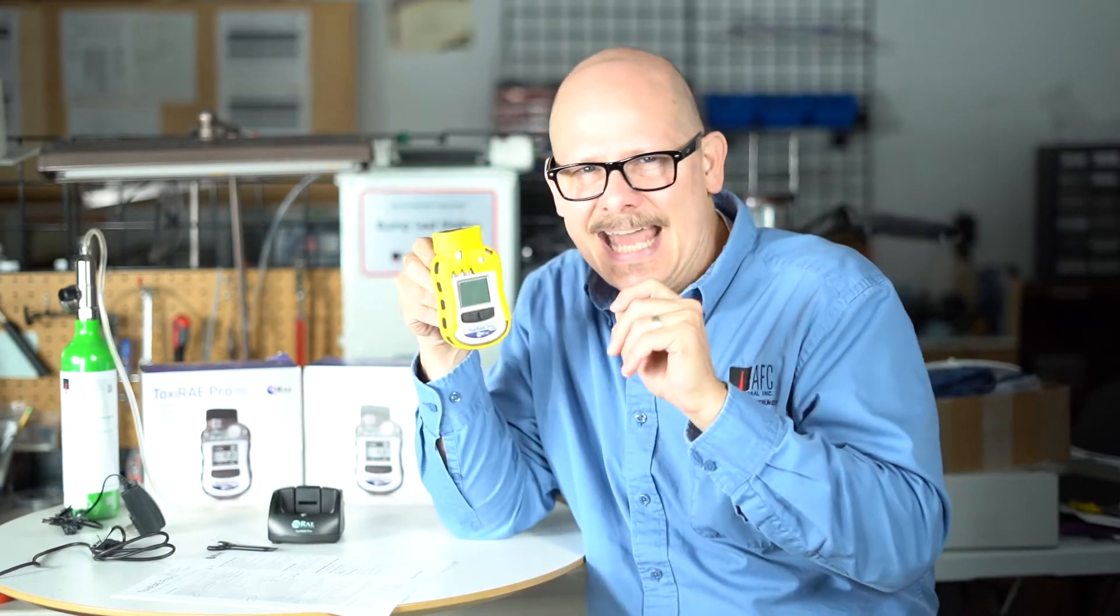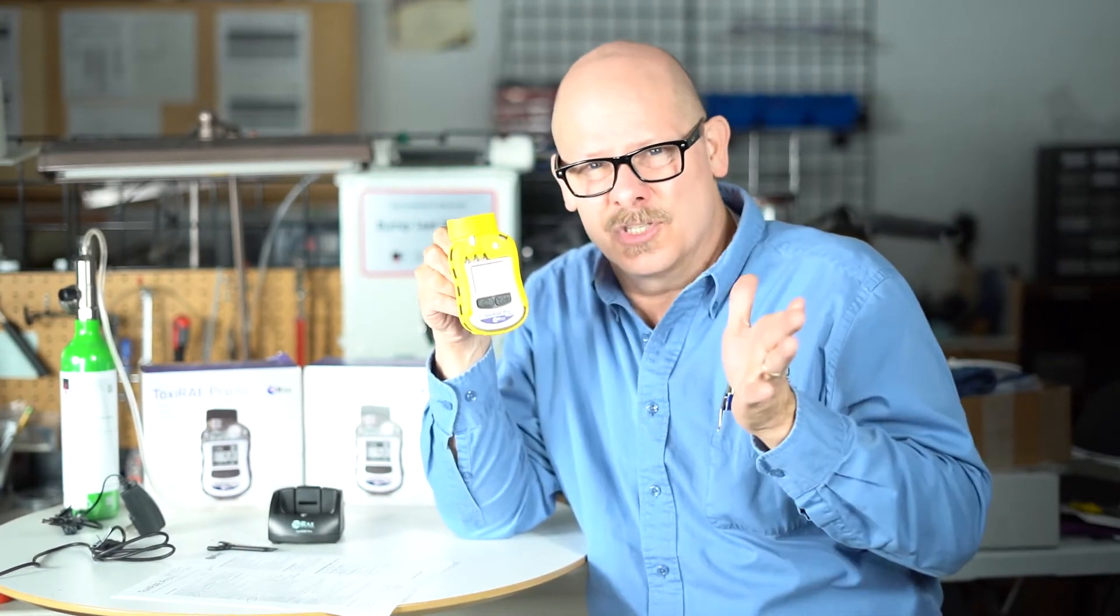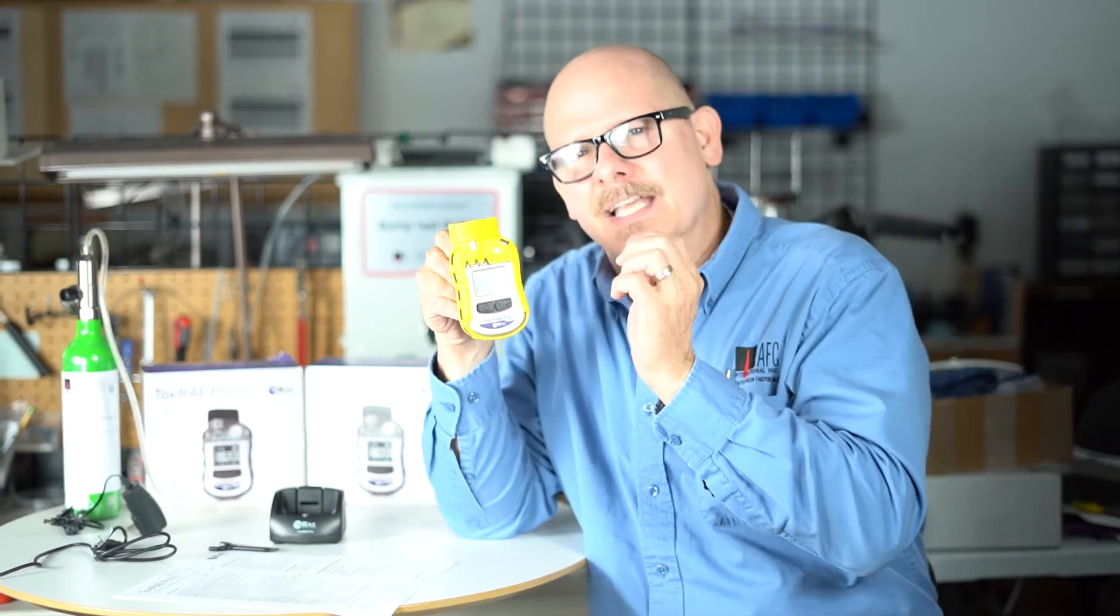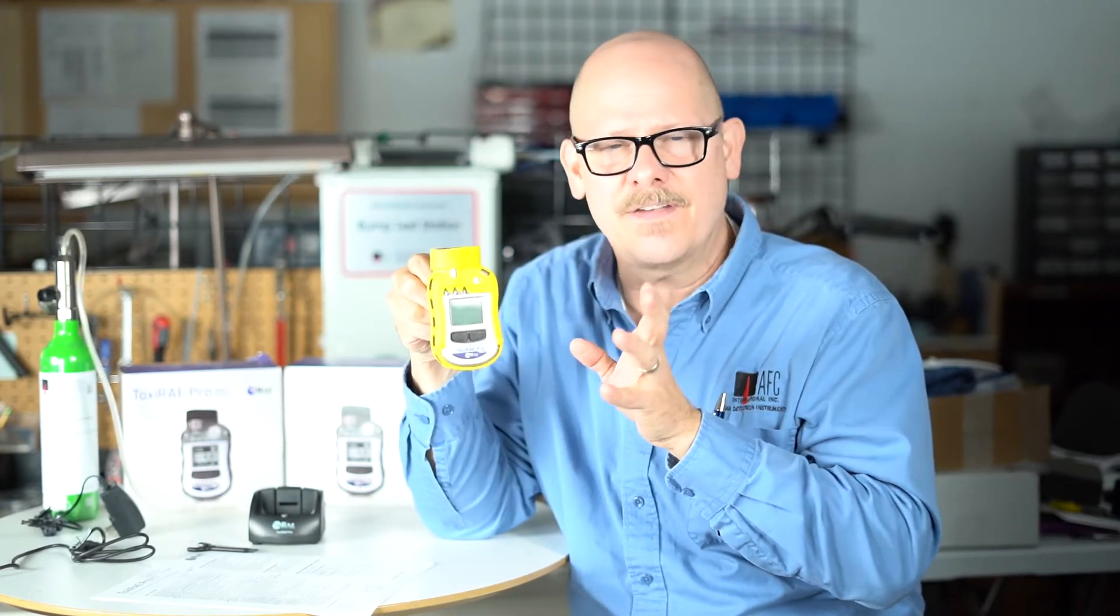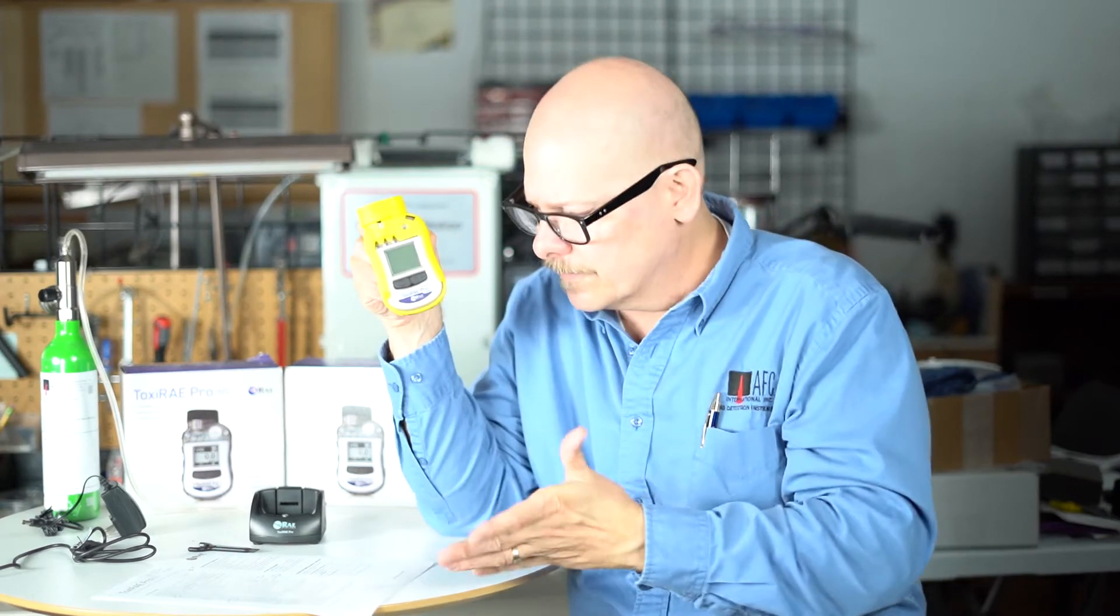It has a T90, time of response, of 15 seconds. So in other words, in 15 seconds, it's going to be to about 90% of true concentration. So it's a very fast detector. Other sensors aren't quite that fast. So the PID has very fast response and very fast recovery.